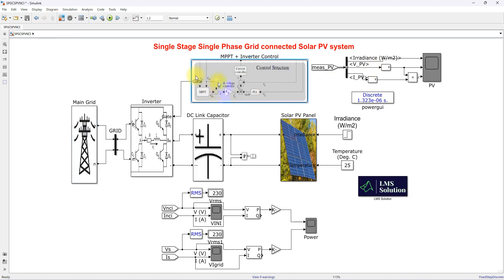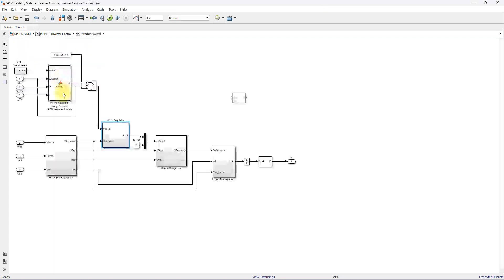The control is known as MPPT plus inverter control. For this we need to measure the PV voltage and current, the DC link voltage, and the inverter voltage and current. The MPPT block is used to extract the maximum power from the PV array — based on voltage and current it generates a reference voltage.